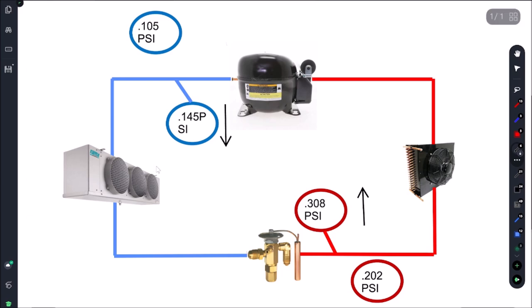So we recovered there, we had the pressures down to like 128, 130, still drawing 69 amps. So the thing I'm not super understanding is why was our head pressure so high. This system had the solenoid open and it was off for like a couple hours. This thing should equalize, this head pressure should have never been this high, it shouldn't go above 200 PSI with this water-cooled condenser pressure. So it's possible we had that bad of a burnout and bad acid in the refrigerant, whatever in the system. But I'm super interested to find out why this happened. So hopefully if my buddy Dave G is listening, you know, he can pipe in in the comments or any of the other refrigeration superstars. If you can explain why my head pressure was at 308 with a system equalized for a couple hours, that would be awesome. Just put that in the comments or whatever, send me a message on Facebook.